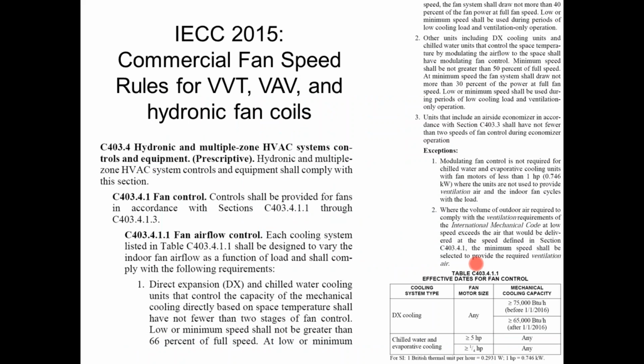This section of the code is really, really, really weird. This was not the way it was intended to be. I've talked to people involved in IECC and ASHRAE 90.1, and this was not the intention, but this is the way it ended up. The intention was to make all systems have two-stage fans or more than two stages. However, when they wrote that language, they put it in section 403.4. And 403.4 in its entirety only applies to hydronic systems, which a normal rooftop would not be, or to multiple zone systems, which a rooftop would only be if I put VAV dampers or VVT dampers or something like that on there. So essentially, you don't have to do the multi-speed fan unless you have zone dampers. If you have zone dampers, then you're going to have to put in a two-speed fan.